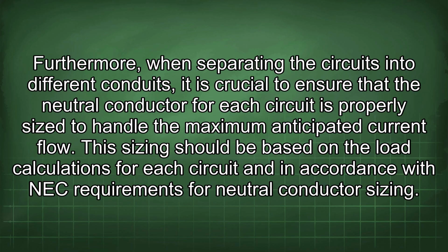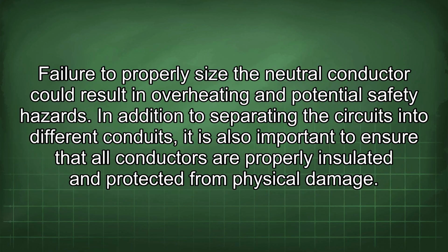Furthermore, when separating the circuits into different conduits, it is crucial to ensure that the neutral conductor for each circuit is properly sized to handle the maximum anticipated current flow. This sizing should be based on the load calculations for each circuit and in accordance with NEC requirements for neutral conductor sizing. Failure to properly size the neutral conductor could result in overheating and potential safety hazards.